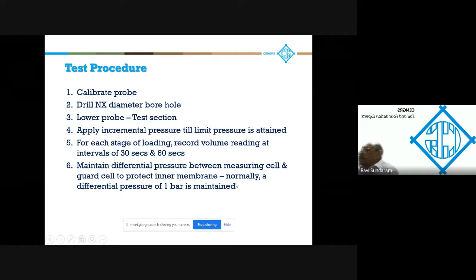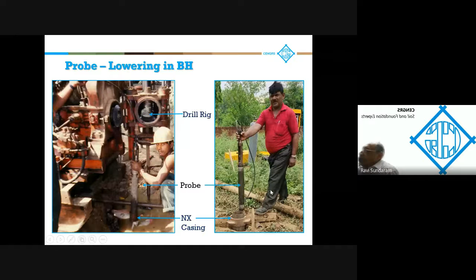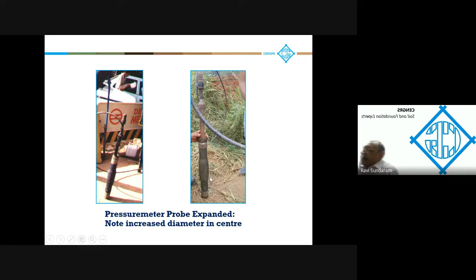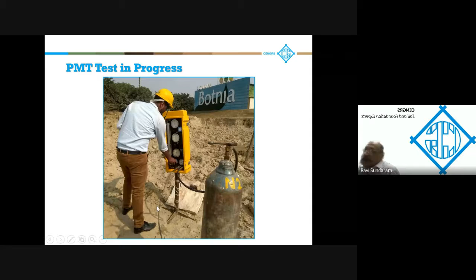Now, this is the probe and this is the NX casing. Here you can see this is the probe which is connected with the coaxial. Now, it is being lowered below the casing for the test section. This is just after the test, when the pressure meter gets expanded. This is a closer view showing you the increase in diameter of the probe in the central portion. Now, this is the test in progress. Again, you remember this yellow box, which is your panel. There's the nitrogen cylinder, and this is the gas tube, and this is the coaxial cable, which is going down to the probe.